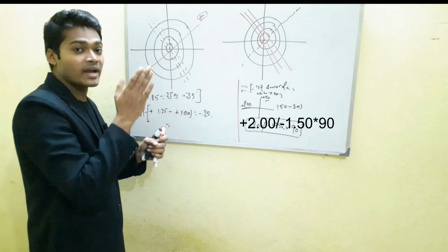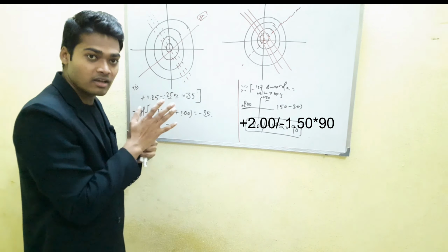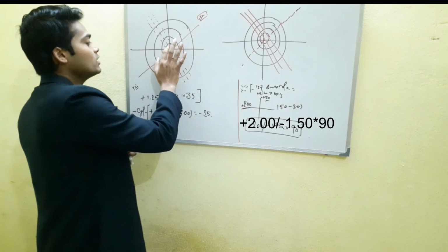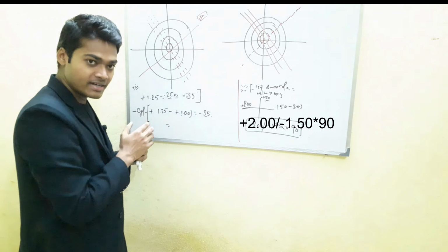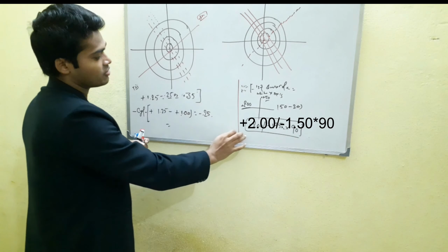What about the second thing? If you want to find out the addition value, after finding this one, simply shift the lens in the upward direction. Basically the addition is always in plus form, and the spherical value you got at the center, you have to rotate the wheel more to the plus side, then write whatever you got. Addition is the near value.